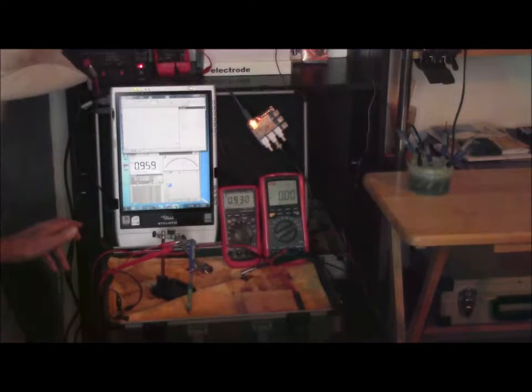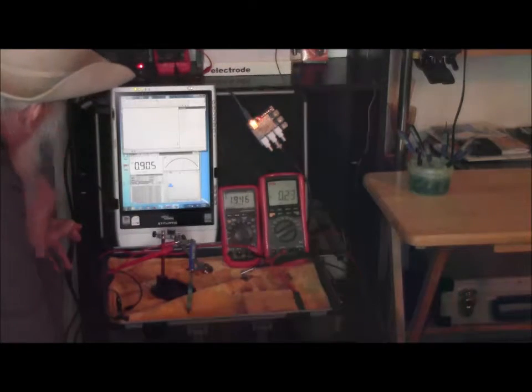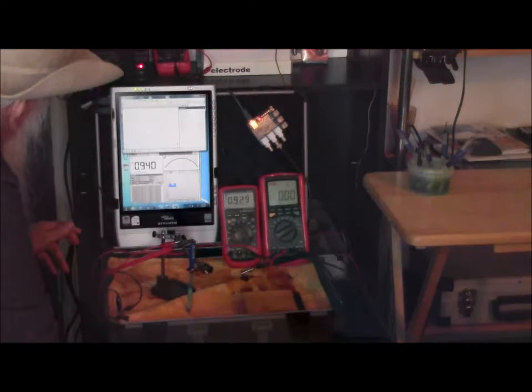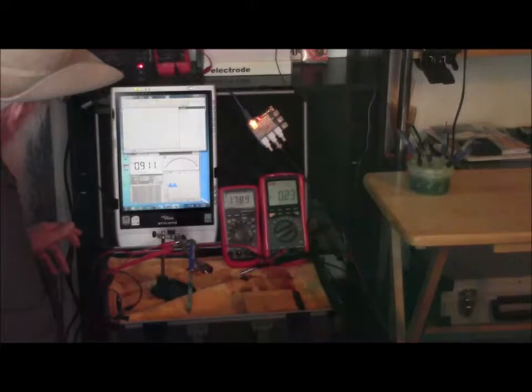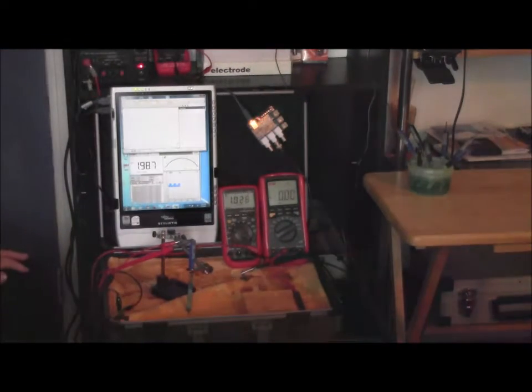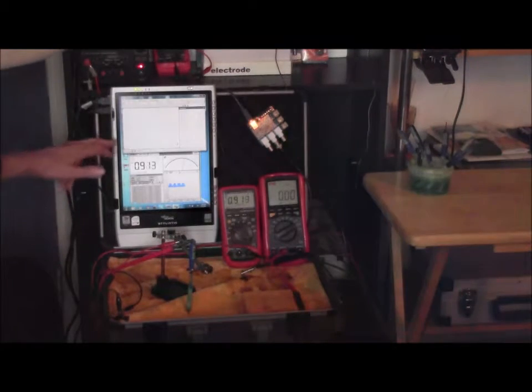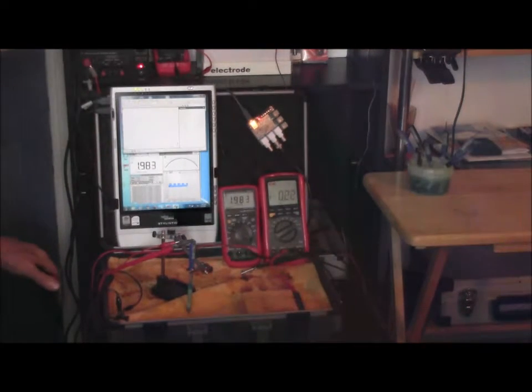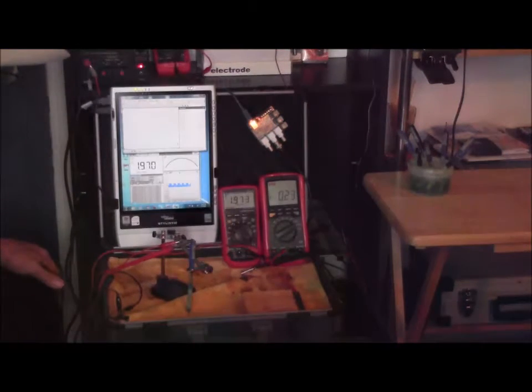I have set it so that it is on for 3 seconds and off for 1.5 seconds. But we can set this to any period of on and off, and we still do not see the kick which we are supposed to see as the polarized potential of the pipeline metal.